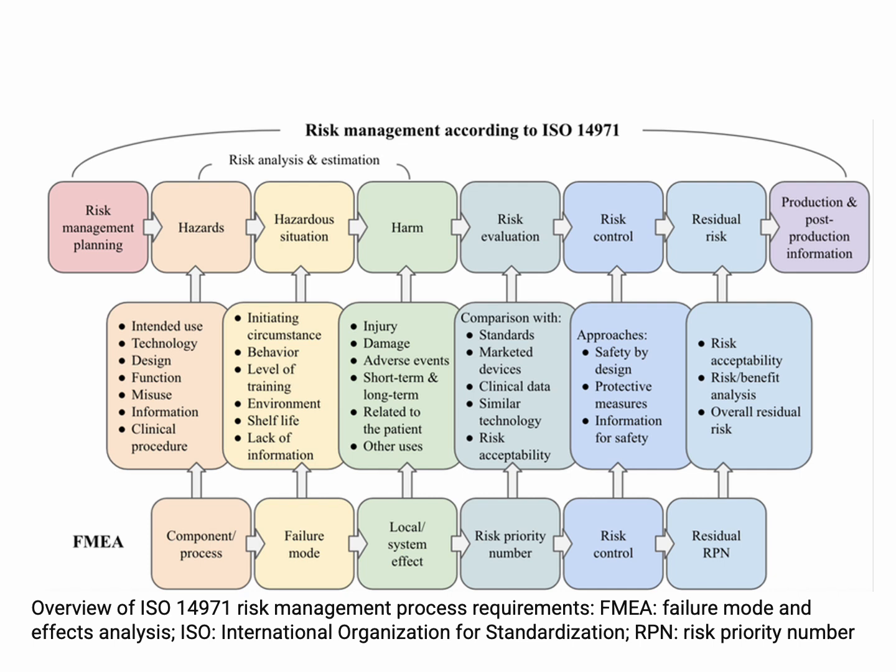So we have to document the fact that we looked into the risks, we learned about the hazards, we did research on the harms and risk, we evaluated the risk, and then we put in place some risk controls, and then we also looked into residual risks. And after all of those different iterations and activities, we then decided to put on the market a safe and valid product that has the performance and reliability as well.